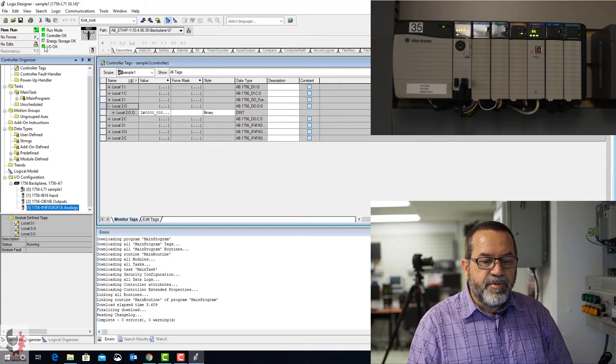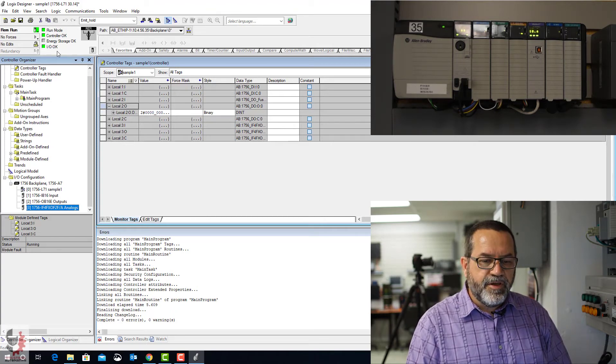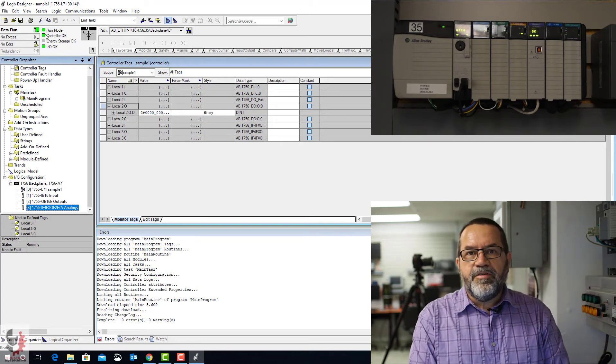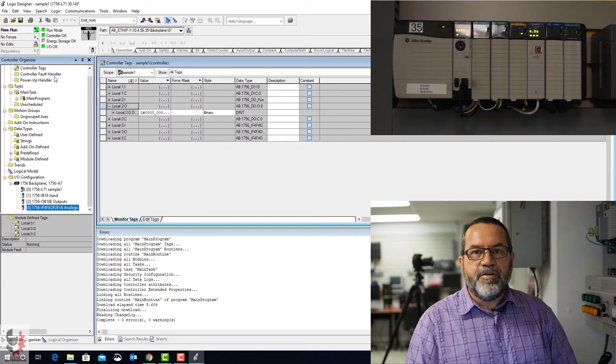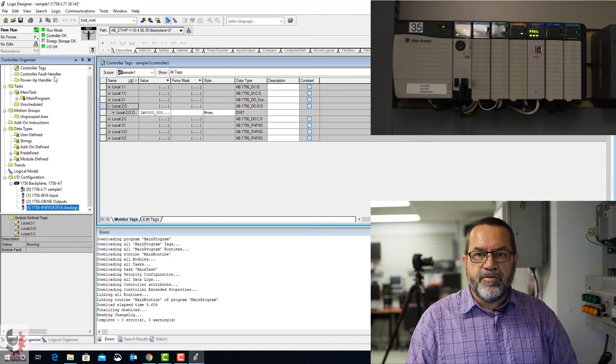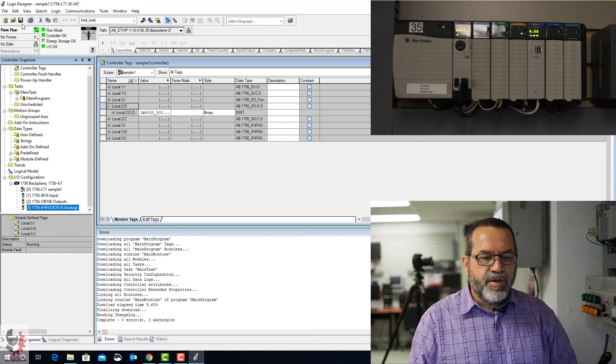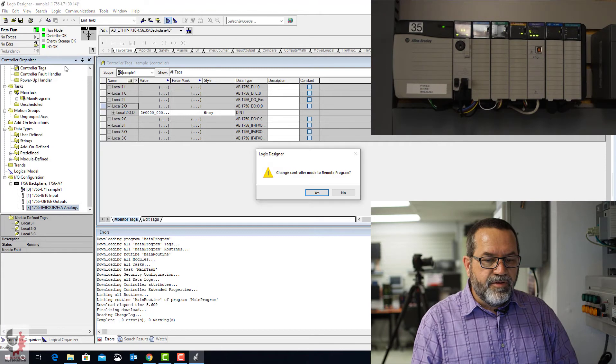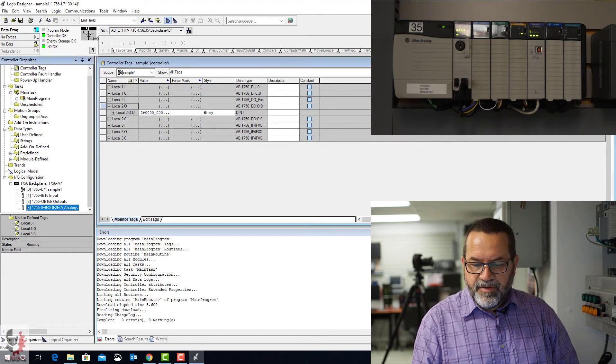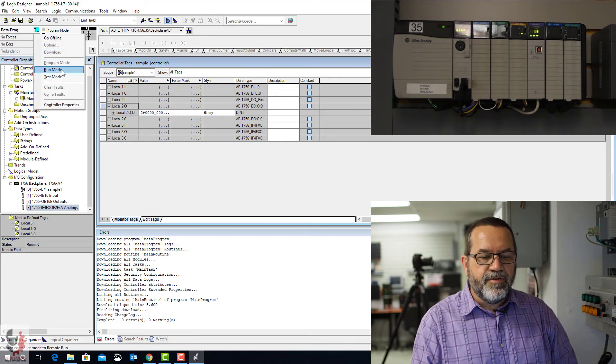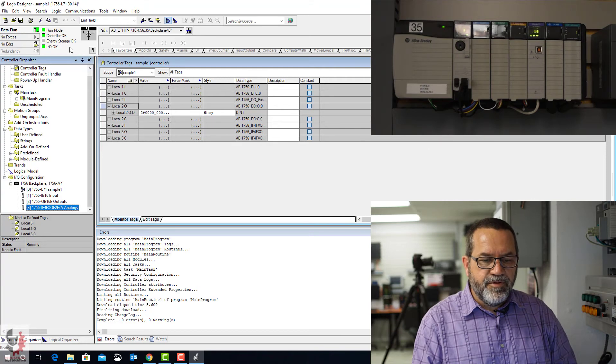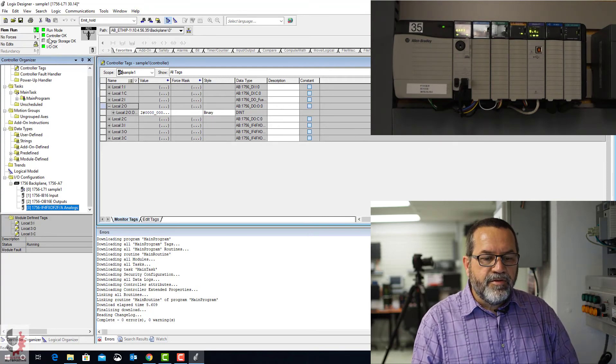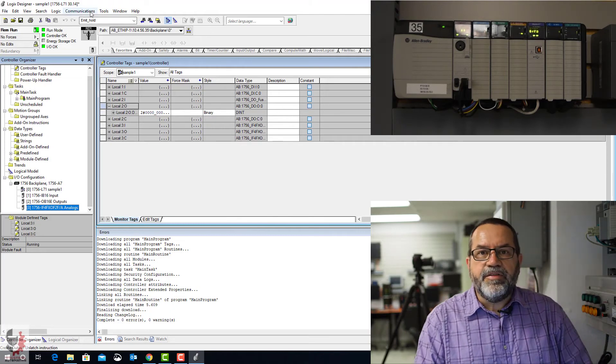Now, if I look up here, I've got a steady green light for input, output, OK. To know if you're talking to your PLC, you have to have all three of these guys green. If they're not all green, then you're not properly talking, and you need to find out why you're not talking. Something's not configured right, or maybe you're just not on run mode. So if I go here, I'll set that to program mode. And notice my green light goes out. So I'm not really in the right mode. So I'll go back to run mode. And now I've got all three green.